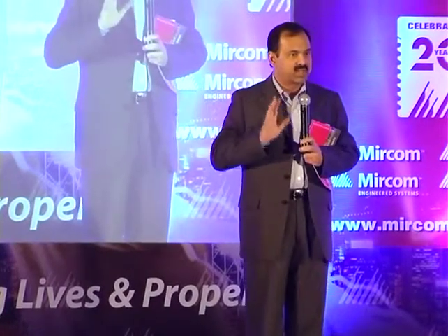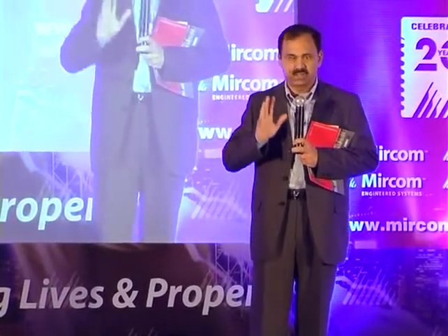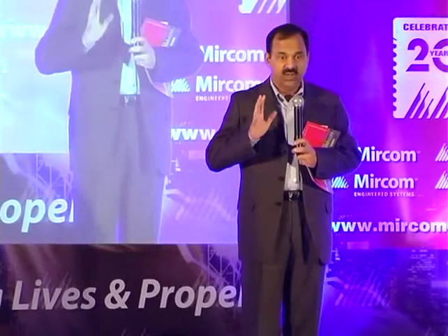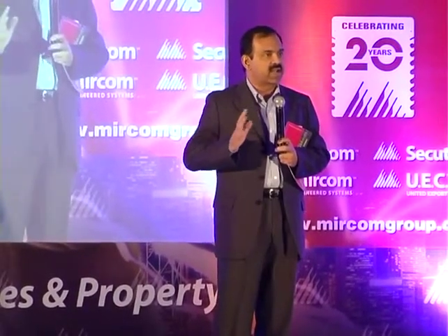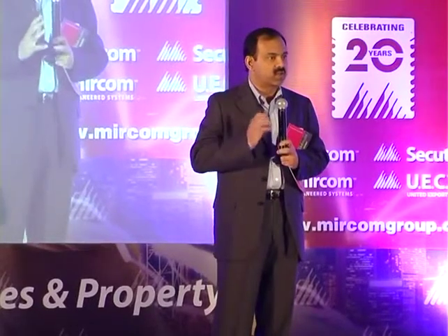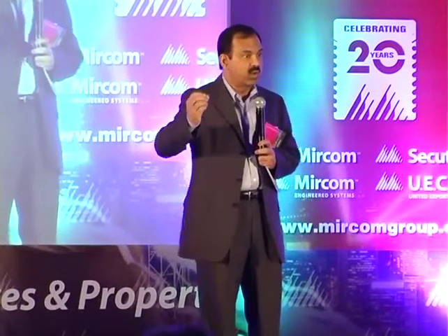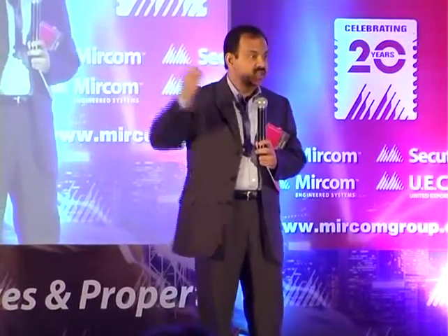I have personally experienced it in many large projects in Dubai, where we had gone in for probably over 31 to 32 panels networked with very complex cause and effect programming, with a combination of fiber and copper. Such massive installations have a lot of requirements in terms of cause and effect. I do remember I had to add on a panel with just one loop and another 50 devices just to ensure that we achieve that particular programming requirement.